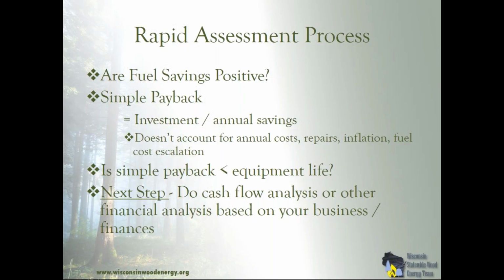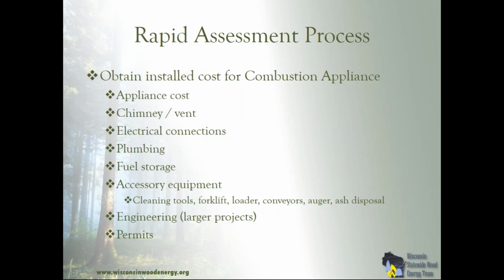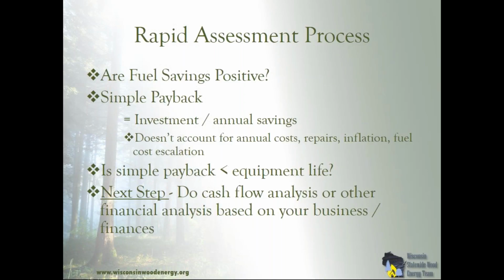So the first question is, are your fuel savings positive? So we already looked at that. The next step is what the simple payback is. So I take all those investment costs, so all these costs, and add them up. So it's investment cost divided by annual savings. So if I was going to spend $5,000 for a unit and I had $2,500 in savings, that's basically a 2-year payback.